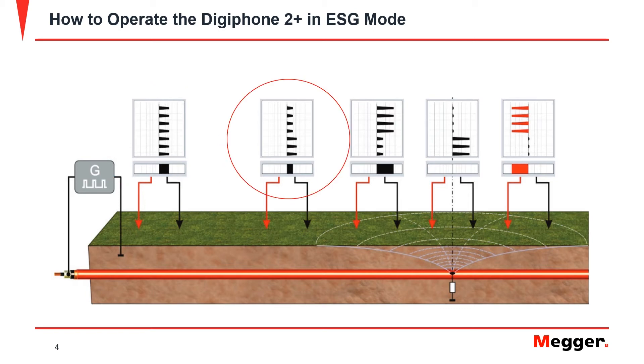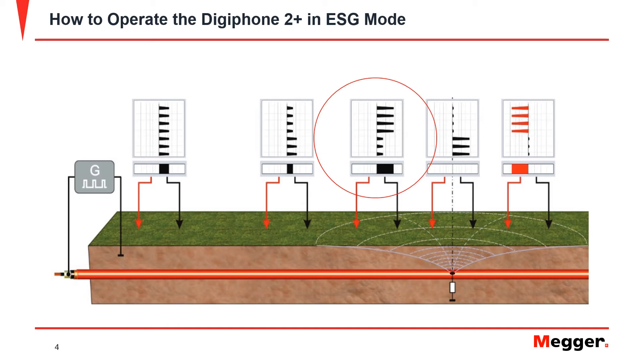At the halfway point between the generator and the fault position on the cable, the signal strength is at a minimum. When we move nearer to the fault, the signal strength increases again. The maximum signal strength is measured when one of the earth spikes is directly above the fault.